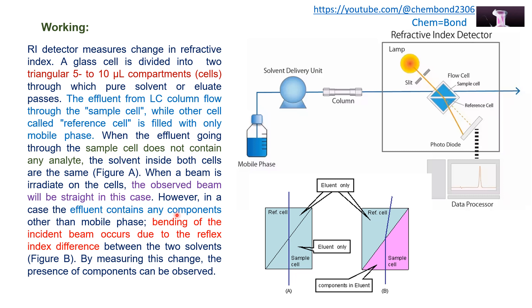However, when the effluent contains any component other than the mobile phase, bending of the incident beam occurs due to the refractive index difference between the two solvents — as shown in Figure B. In Figure B, one compartment is shown in blue containing only the mobile phase, and the other in pink containing the mobile phase along with the solute. There is now a difference in refractive index, and as the light passes through the sample cell it bends. That difference in refractive index is measured and is directly proportional to the amount of sample in the cell. By measuring this change, the presence of the component can be determined.